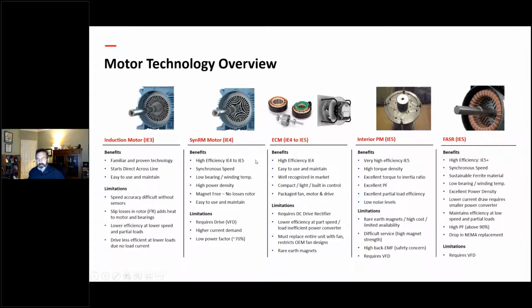IE is an IEC standard. If you're not all that familiar with it versus NEMA, the reason we use it is because NEMA really only has a standard up to what we call IE3. That's a premium energy efficient motor. There's terminology being used out there for super premium, which would be like an IE4, and ultra super premium, which would be like an IE5 motor, but there's really no NEMA standard for it. And the IEC scale from IE3 to 5, there's actually a scale, so we default to using it because there's no NEMA standard.